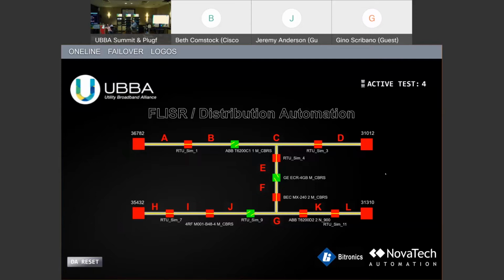If you're in a substation, there's literally going to be a pistol grip handle that's going to have rotated and locked, and you are going to have to go on site and reset that. If it's a recloser, a lot of times we have SCADA controls where we can do that remotely. We can try to remotely control that device. After we've sent somebody to the field, they've inspected the line, they've isolated something, they'll call back in on the radio to operations and say, hey, we think we solved the problem. Go ahead and reclose that breaker and re-energize it. This recloser scheme is trying to do all of that stuff automatically for us to improve the quality of service that we're providing to our customers.